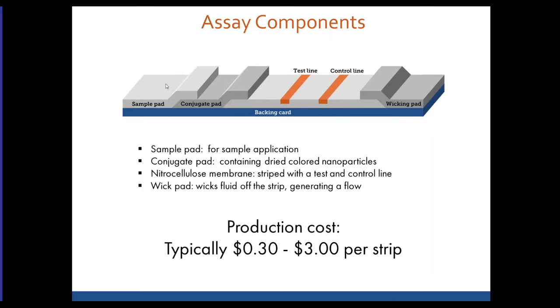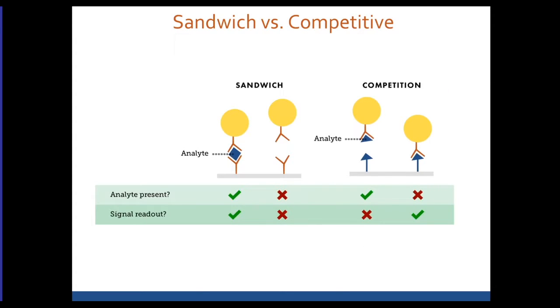A lateral flow strip is a pretty straightforward technology. You have a sample pad where you apply a sample; liquid from the sample flows along, dissolving colored nanoparticles from the conjugate pad. Those colored nanoparticles flow along the strip to the test line where, in the presence of the analyte, they give rise to a signal, and then they're wicked along into the wicking pad or sump. It's simple in conception but involves quite complicated chemistry. One appealing aspect is that these strips can be made for as little as 30 cents each at large scale.